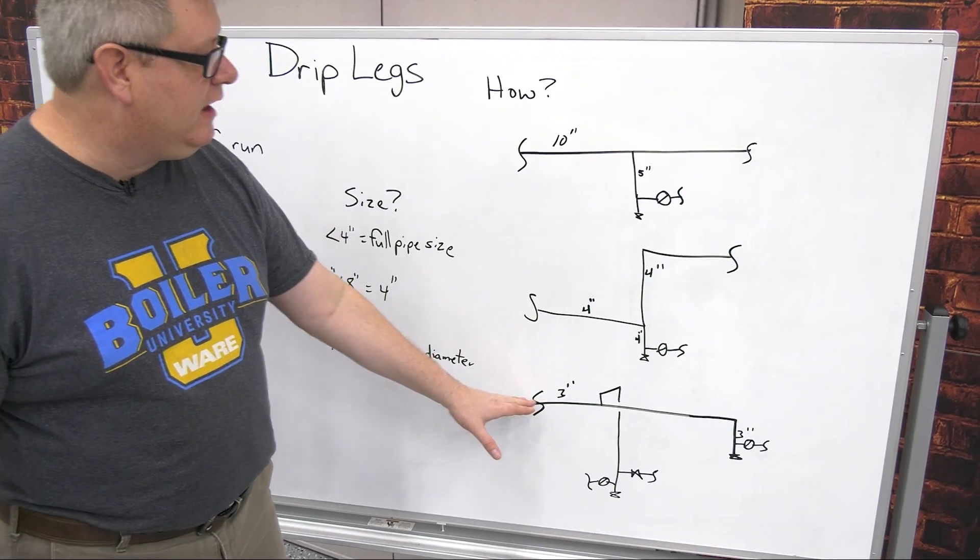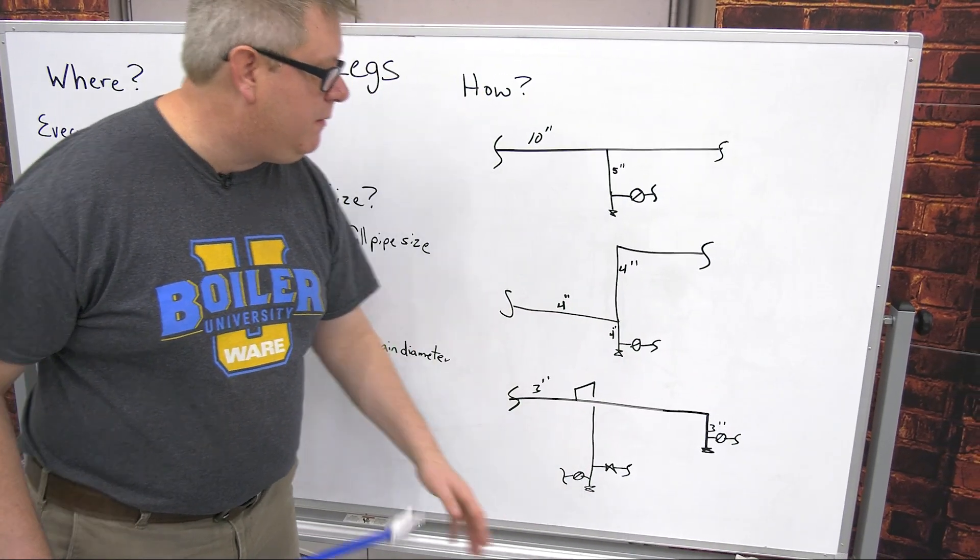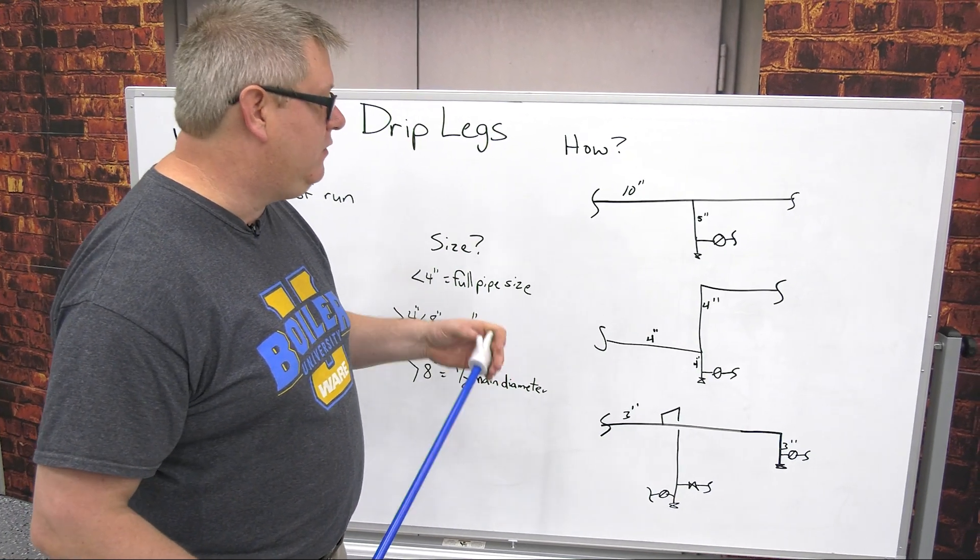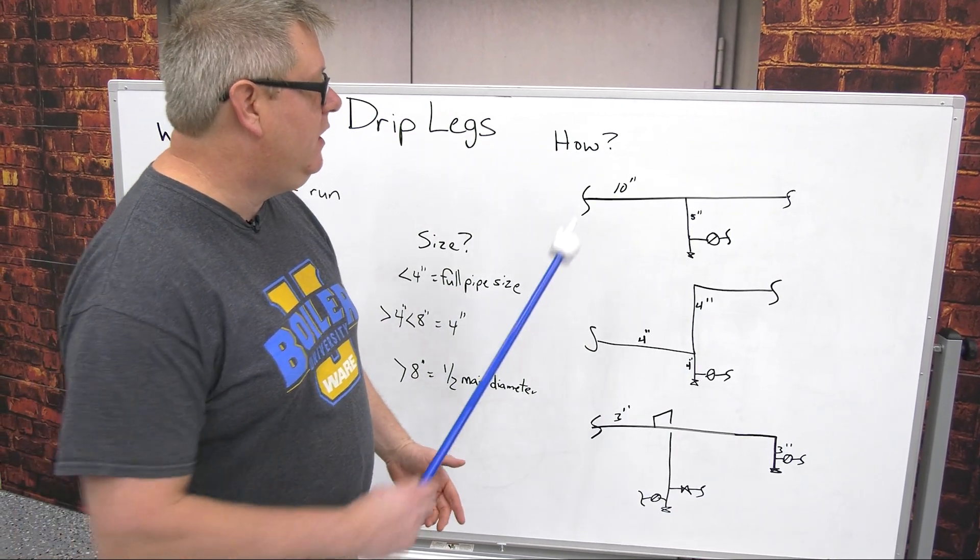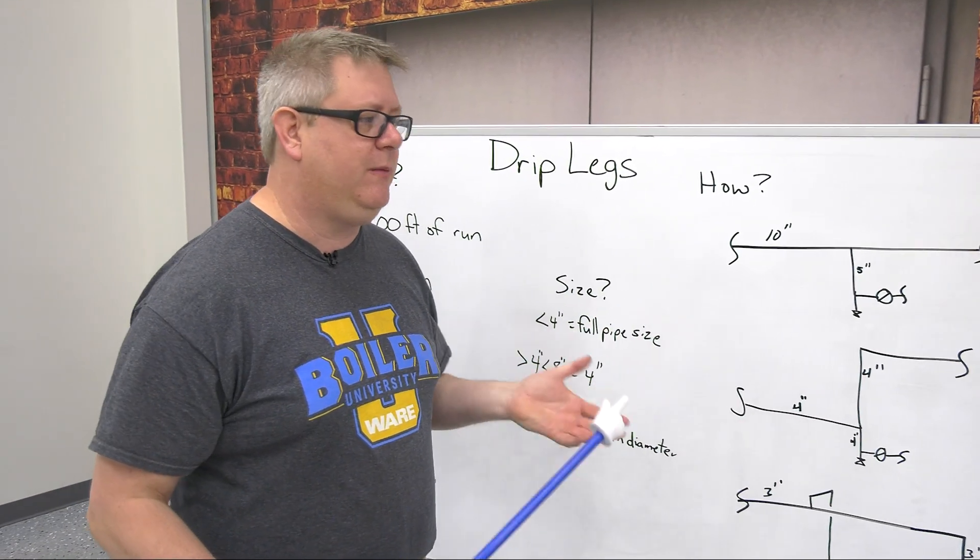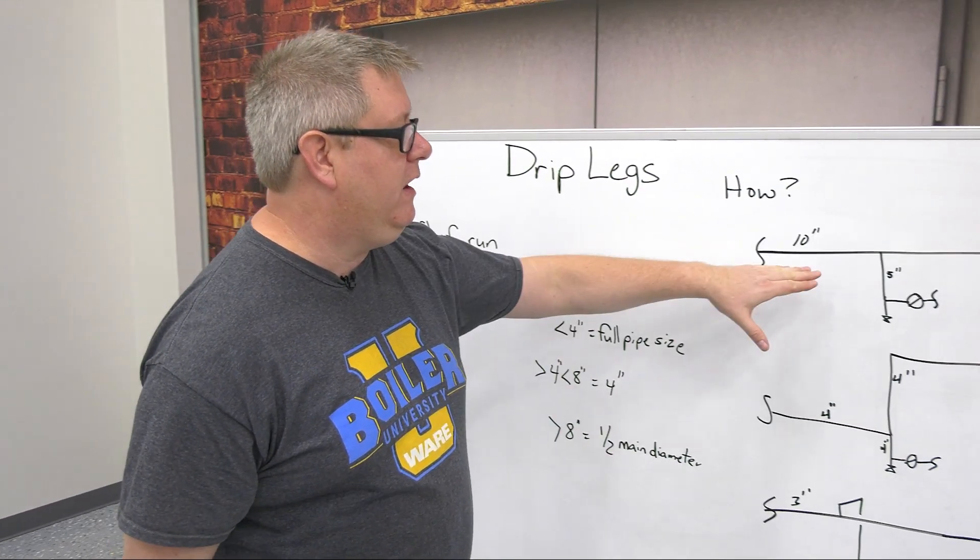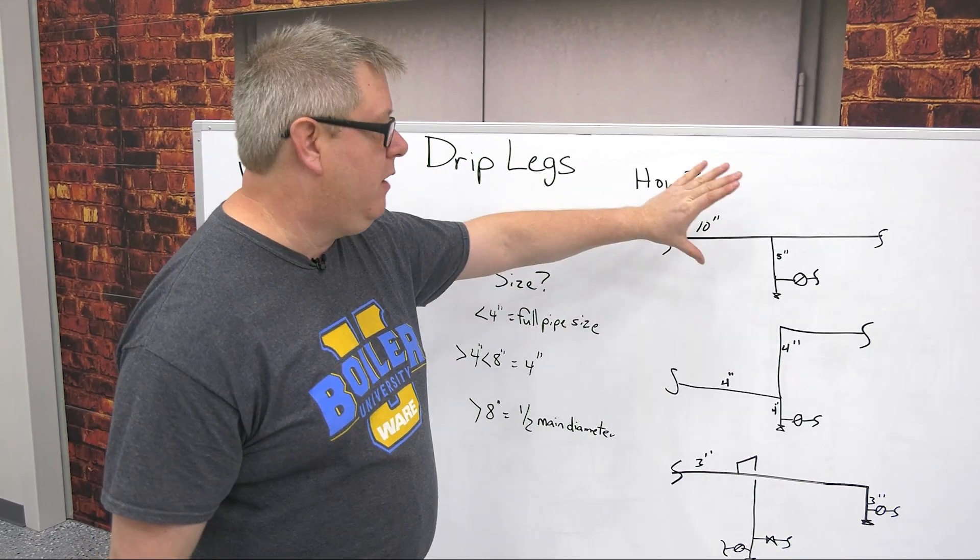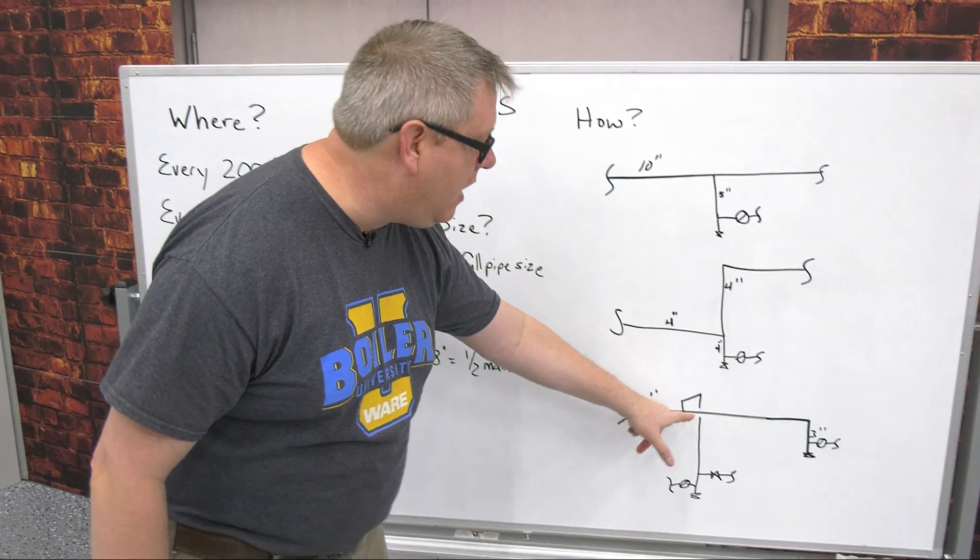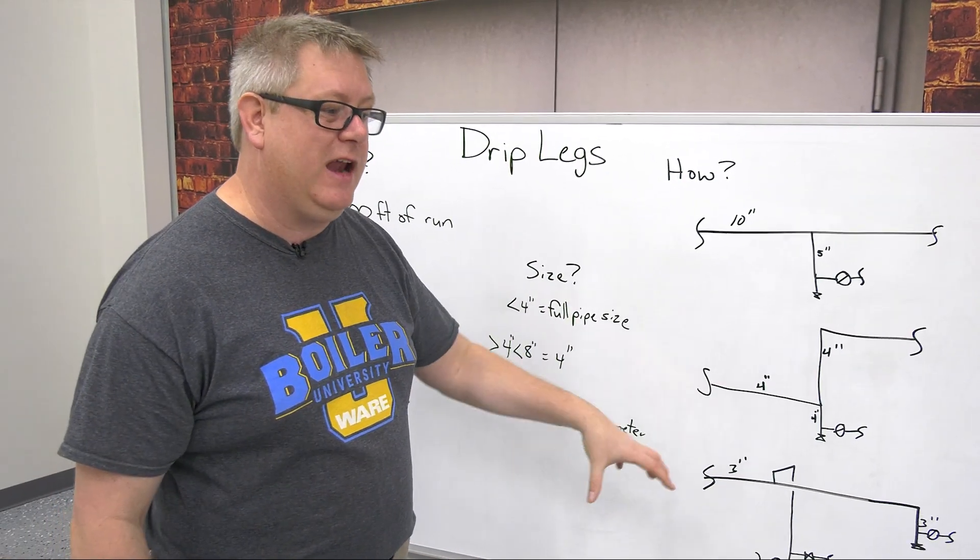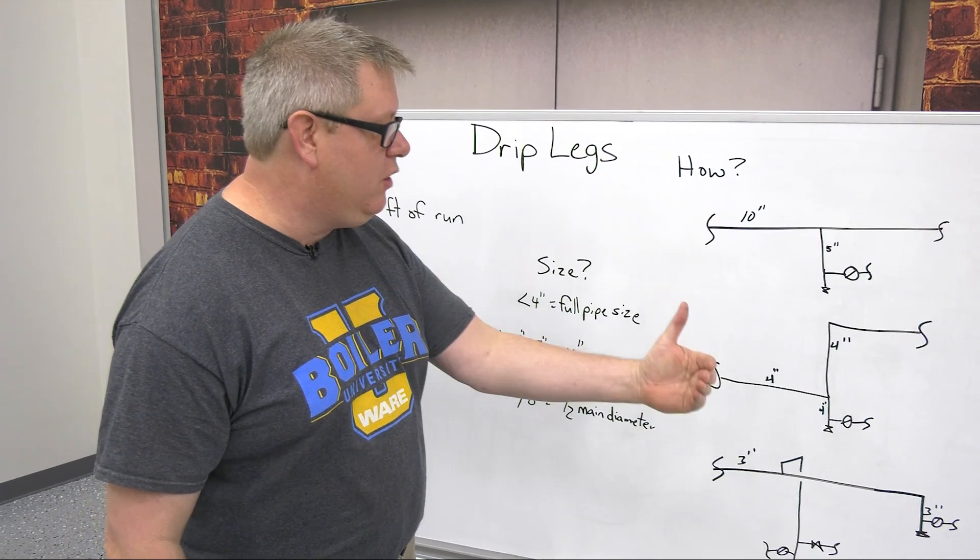In this instance, we're taking a drop off to a piece of equipment. One tendency when somebody's making a drop to a piece of equipment is to pull off the bottom of the steam line because it requires the least amount of fittings and welds. But you can see from this example, that's how you put a drip leg on a main. So if we pull off the bottom of the pipe, we're going to get all the condensate because we're creating a drip leg, but it's going to go into our equipment.